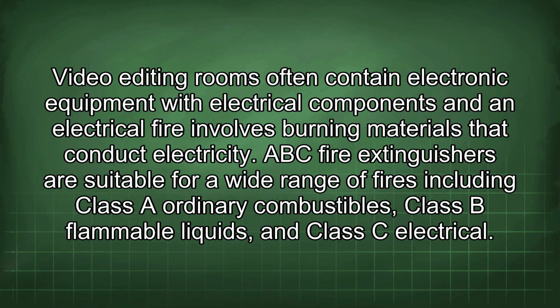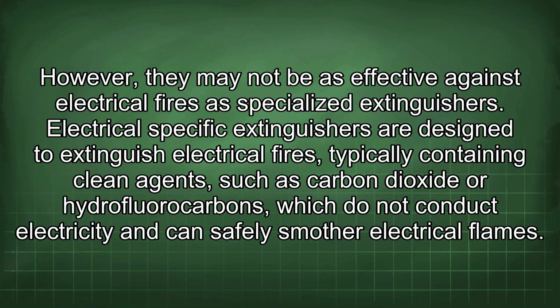ABC fire extinguishers are suitable for a wide range of fires, including Class A ordinary combustibles, Class B flammable liquids, and Class C electrical. However, they may not be as effective against electrical fires as specialized extinguishers. Electrical-specific extinguishers are designed to extinguish electrical fires, typically containing clean agents such as carbon dioxide or hydrofluorocarbons, which do not conduct electricity and can safely smother electrical flames.